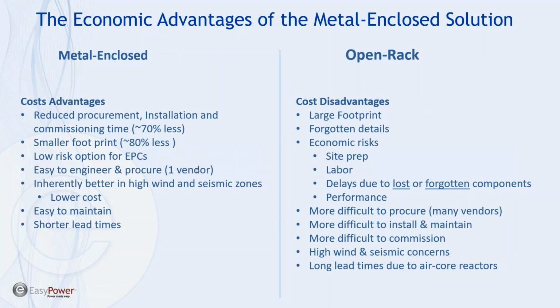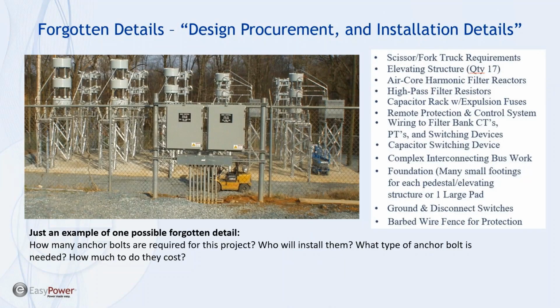In the open air solution, you have to get up on a bucket truck or scissor lift. You have to get somebody there to do that. Somebody's licensed to do that. We're trained to do that. You have to put on a harness. So to change out a capacitor is much more difficult. And then finally, shorter lead times. Metal-enclosed systems always have shorter lead times, partly because air-core reactors have lead times that are typically in the order of 26 weeks. And then finally, there's always the forgotten details.